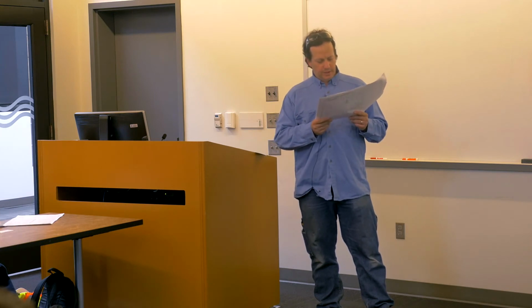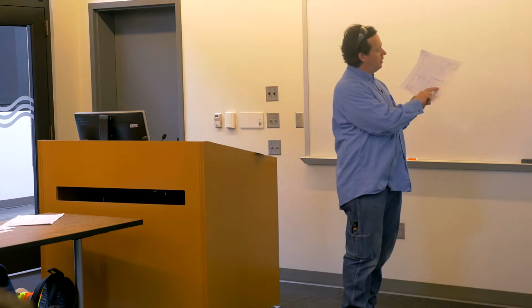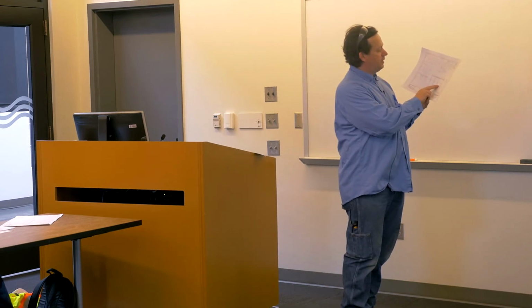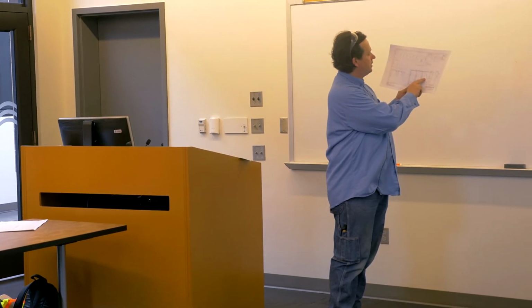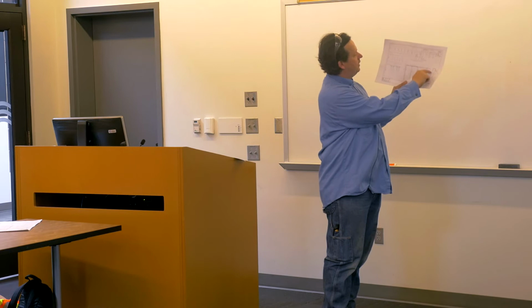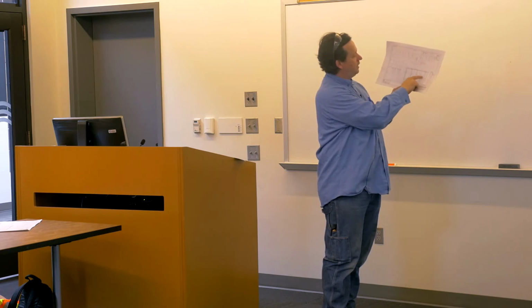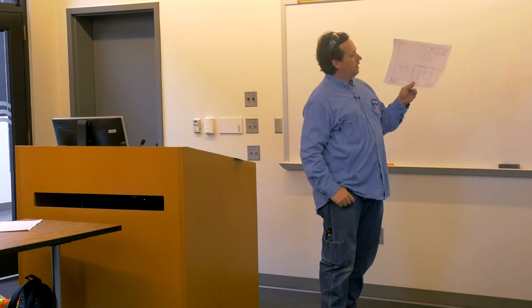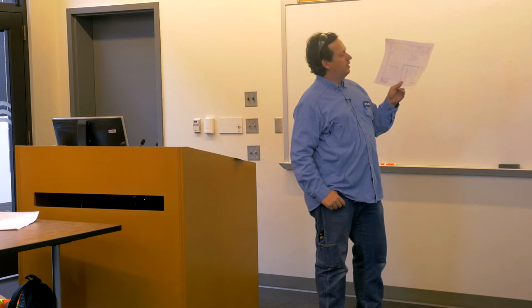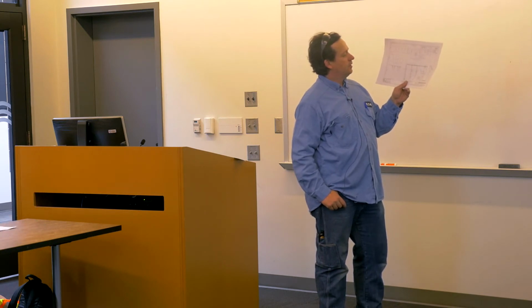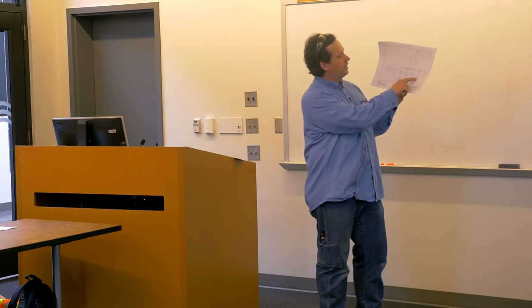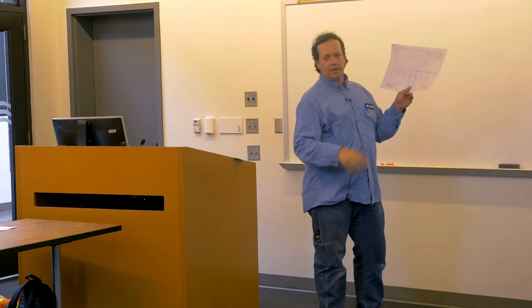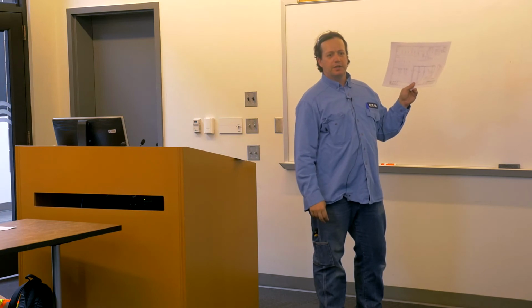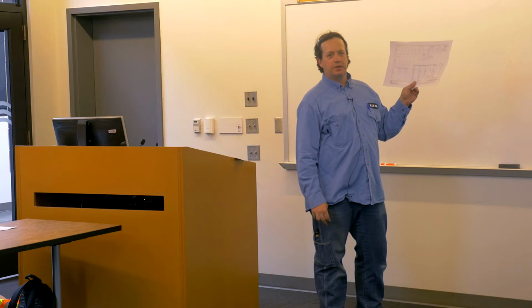So here on this one line schematic, in section 2C, that's where you'll see your PT. It's actually wired up in a wide open delta connection. So open delta, you're just taking the B phase and grounding it. You're using A phase and C phase with that.